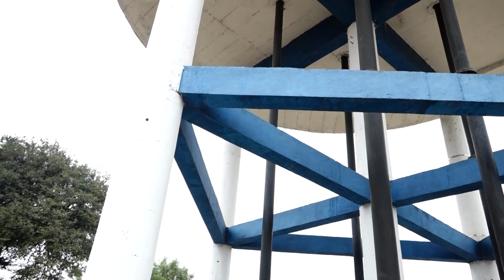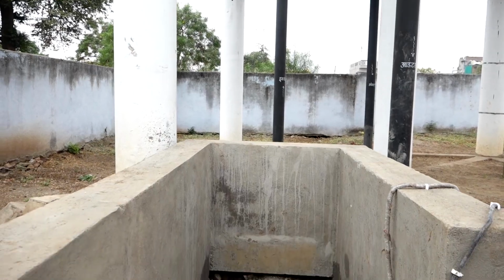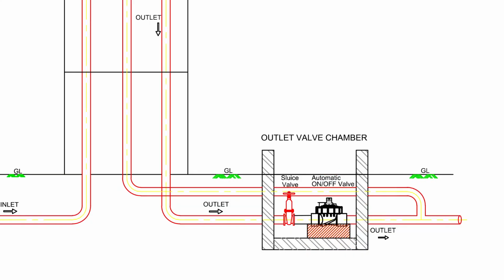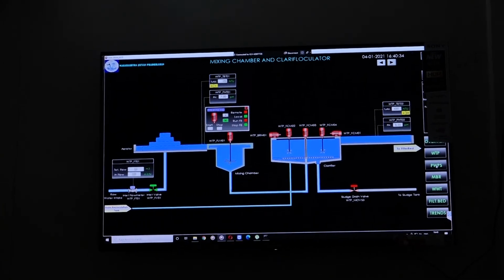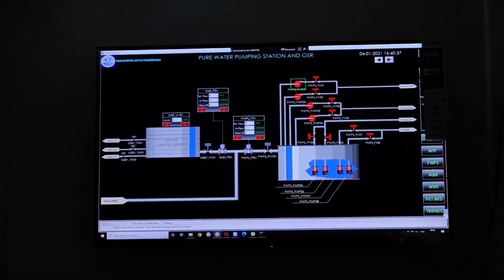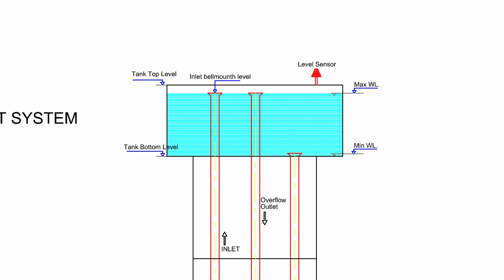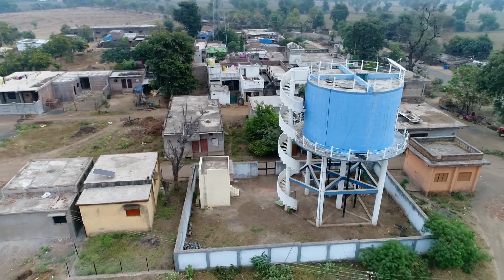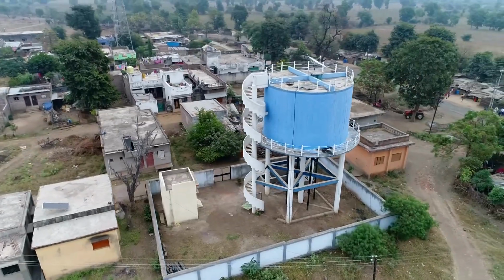As per the schedule of the water supply, the command is given to the on-off valve at the outlet of the ESR. An auto command is given by the controller to shut off the on-off valve by keeping a minimum of 1 meter water level in the ESRs for an emergency such as fire, etc.